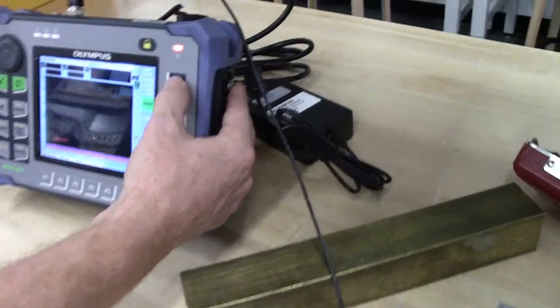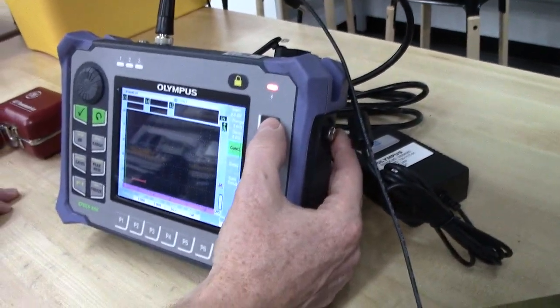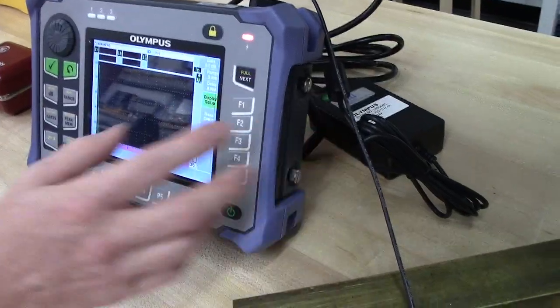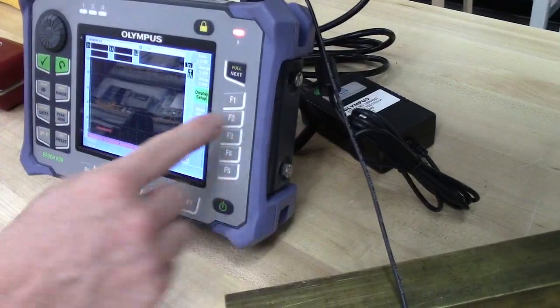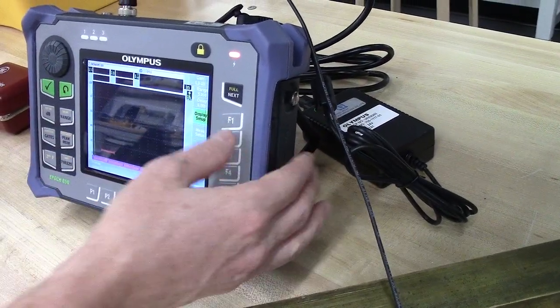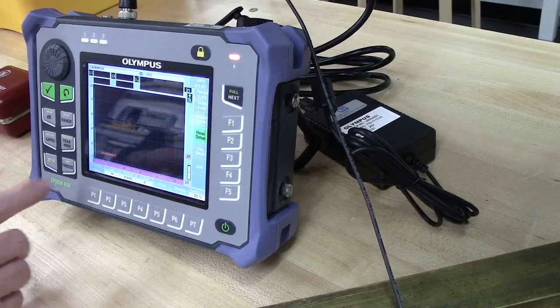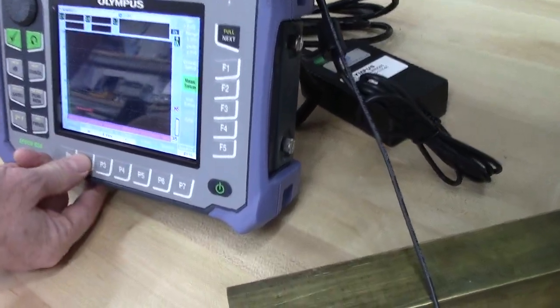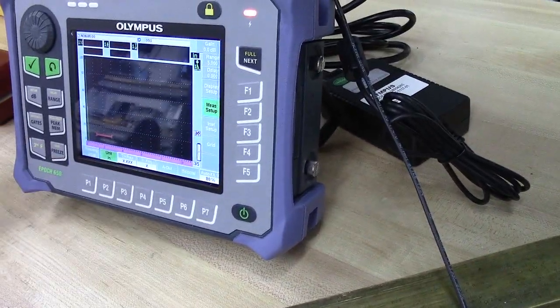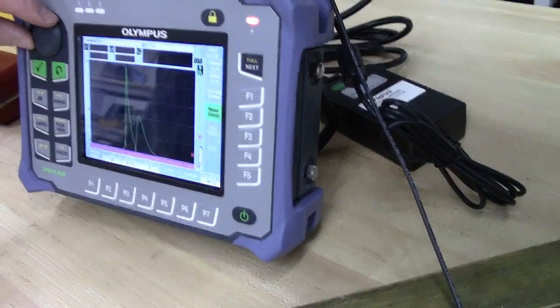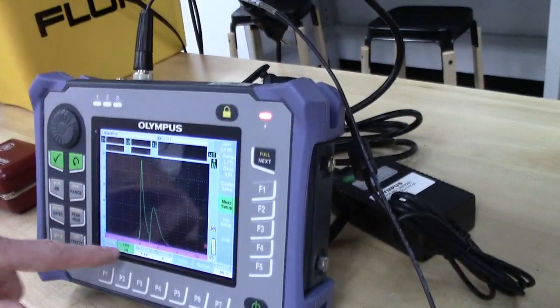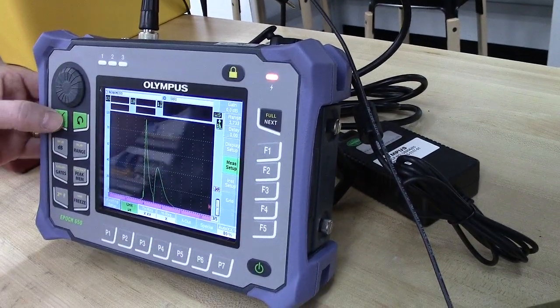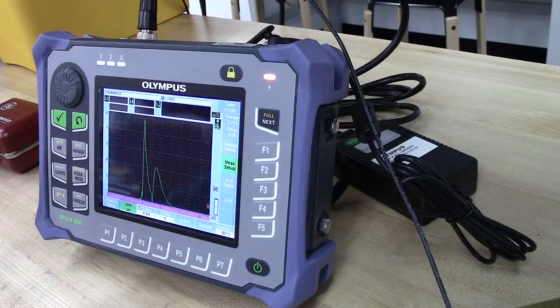So here we can cycle through the different measurement, or the different options. And on this menu, measurement setup. There we want to come and pick the unit. We're set to inches. And we can rotate it over here until we get to microseconds. We can press this to select that.